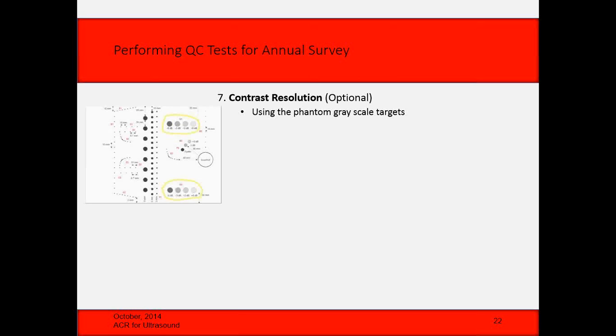You can test this kind of with a phantom with the grayscale targets in the phantom, but the thing is that an ultrasound system these days typically has about 90 dB of dynamic range. That has to get compressed down to about 60 dB because that's about all the human eye can see in dynamic range. And the targets that they put in these phantoms are typically at the most maybe plus and minus, or maybe 24 dB it'll cover, plus and minus 12 dB. So obviously that's, you know, like nowhere near what the system is actually capable of. So basically, if you can't see all those grayscale targets, you've got something really messed up.